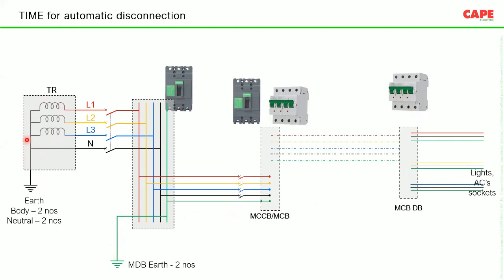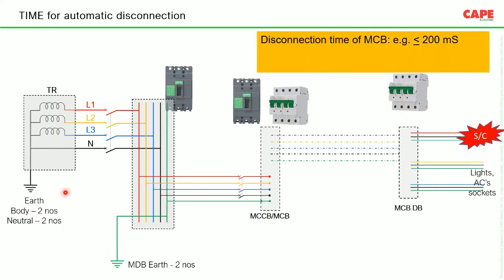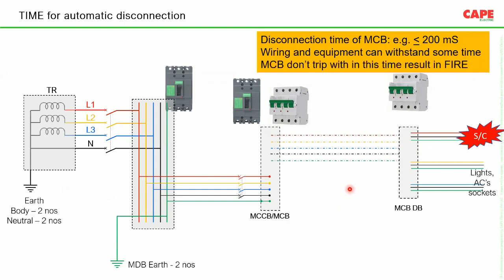TT system, in the sense, the transformer neutral is connected to an earth pit and the panel board earth bus bar is connected to a separate earth pit. As a result, it becomes a TT system, but sometimes underground these are also connected. Then it becomes an inefficient TN-C-S system, which is very dangerous. Disconnection within the recommended time of 200 milliseconds may not happen. You must understand that wiring and equipment can withstand fire or a higher current only for a short time. So basically, the disconnection may not happen.